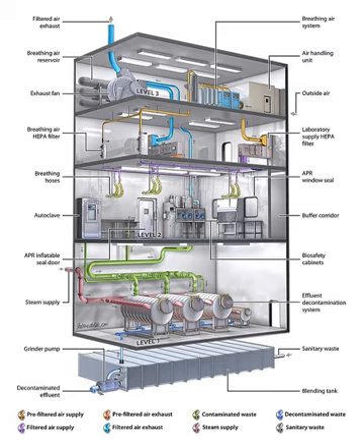In a protective suit laboratory, all work must be done in a class 2 biosafety cabinet by personnel wearing a positive pressure suit. In order to exit the BSL-4 laboratory, personnel must pass through a chemical shower for decontamination, then a room for removing the positive pressure suit, followed by a personal shower. Entry into the BSL-4 laboratory is restricted to trained and authorized individuals, and all persons entering and exiting the laboratory must be recorded. As with BSL-3 laboratories, BSL-4 laboratories must be separated from areas that receive unrestricted traffic. Additionally, air flow is tightly controlled to ensure that air always flows from clean areas of the lab to areas where work with infectious agents is being performed.